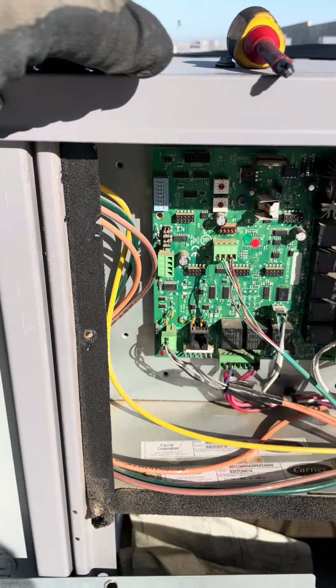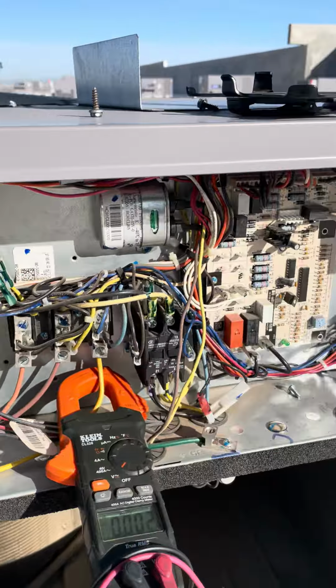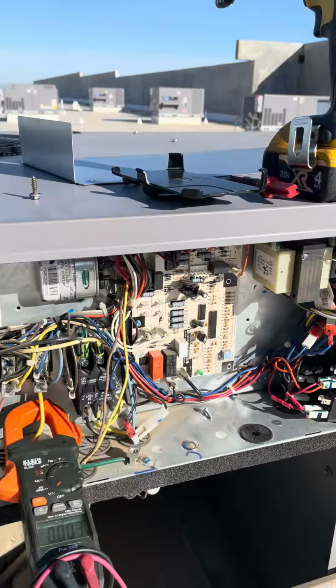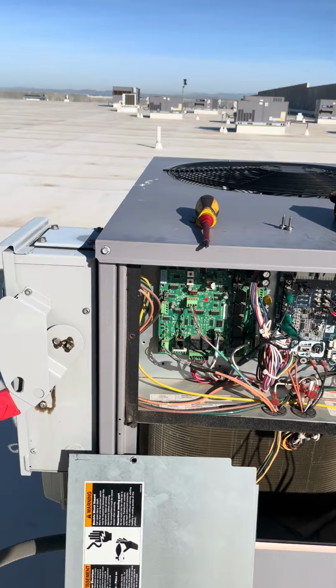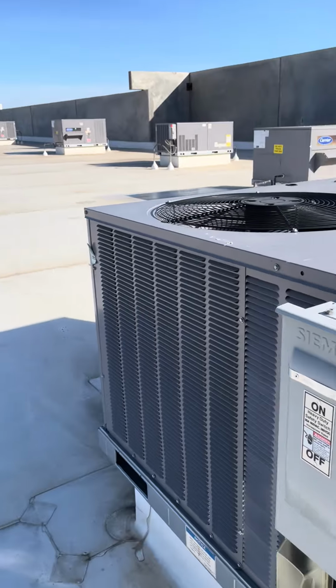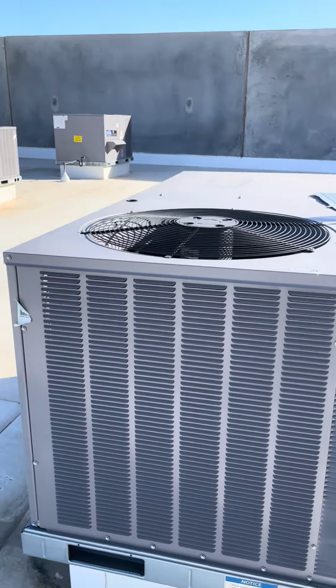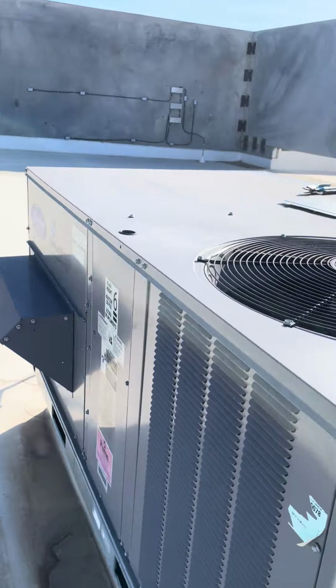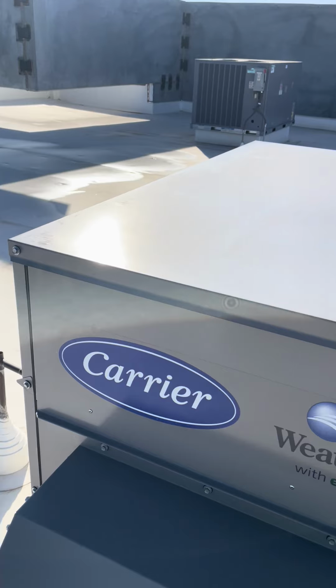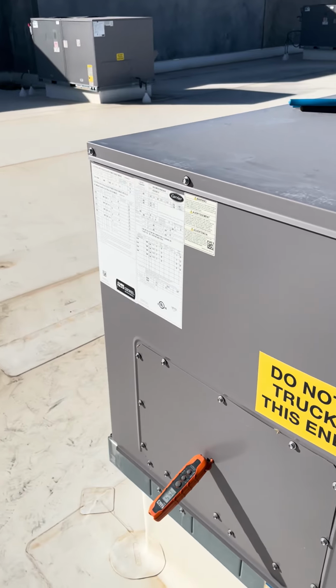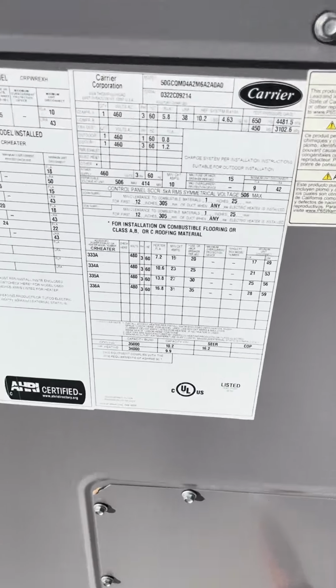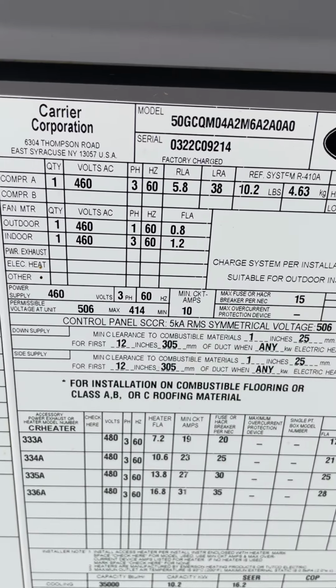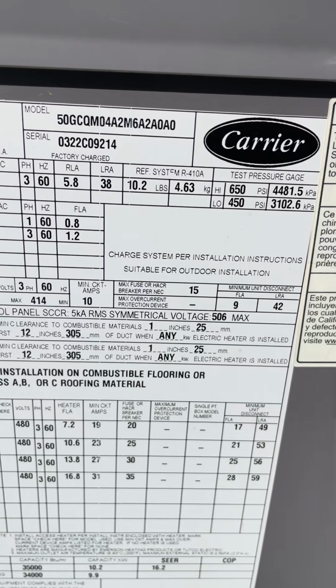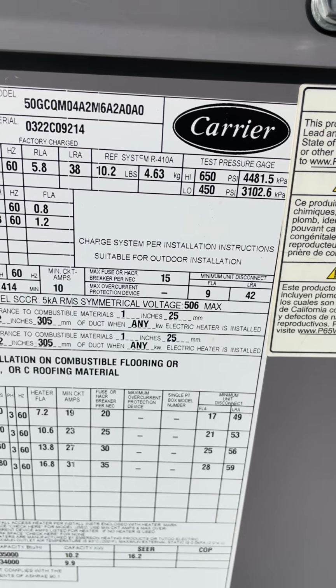We're working with one of the newer Carrier units that is having an issue where it's not going into cooling. At least it's running the compressor and the condenser fan, but it's still heating. I'm going to demonstrate and show you what we're looking at. Working on a Carrier 50GCQM04.